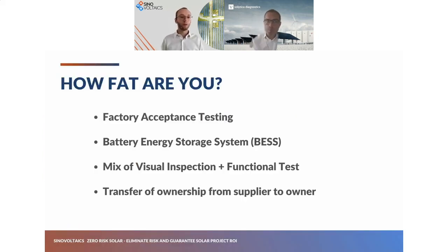So just to be sure everyone is on the same page, when we talk about FAT here, we are not going to talk about how you will lose weight before the summer break. But we are going to talk about the factory acceptance testing for battery energy storage systems. So those are about 20-foot, 40-foot containers full of batteries. And when we talk about FAT, it's usually a mix of tests, including visual inspection, as well as a final test to be sure that the performance is good enough.